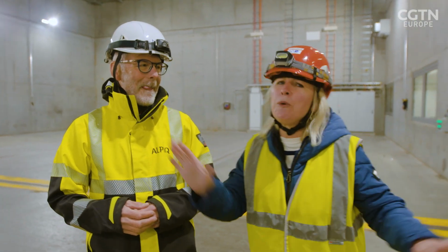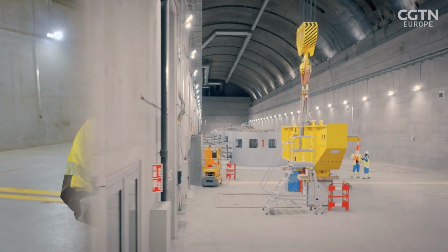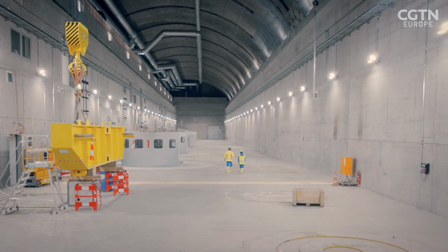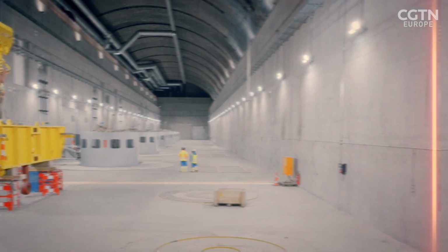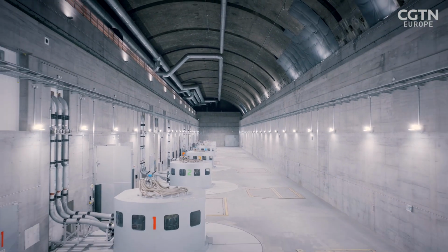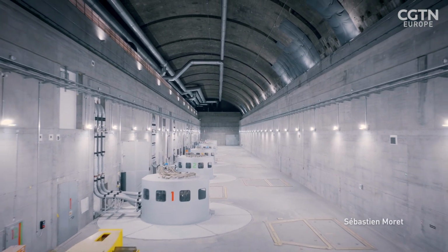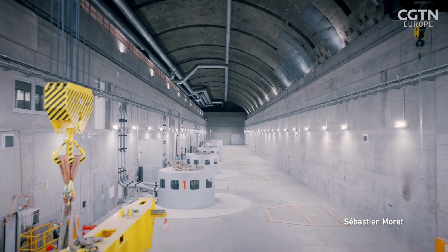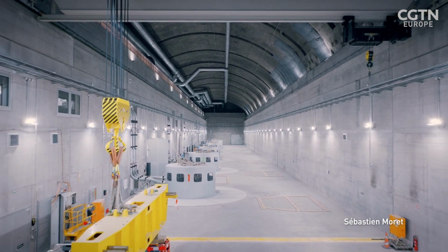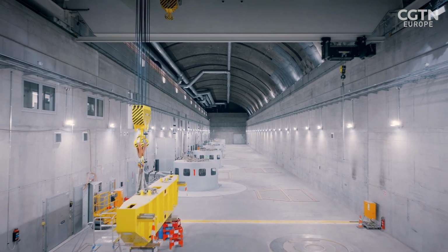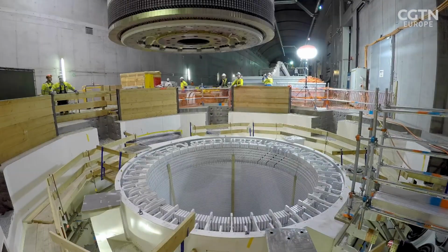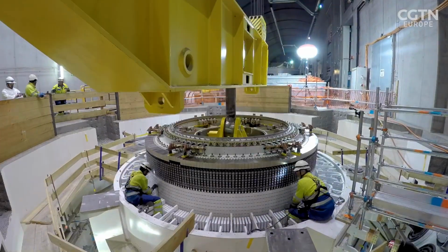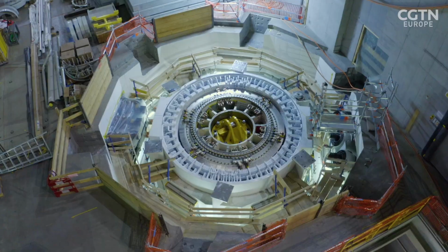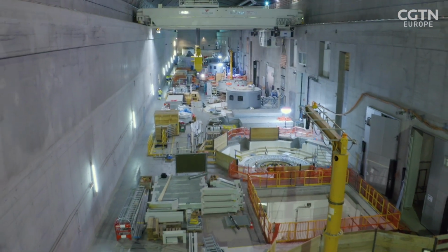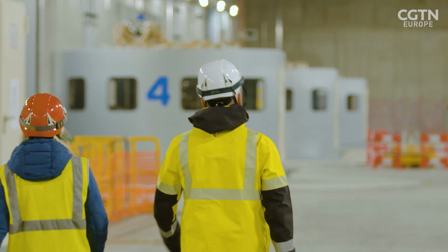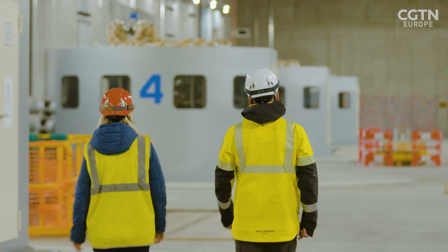Big numbers. They don't do small numbers here. Everything's big numbers. I'm on a tour of the Nant de Drance, a pumped storage hydro facility. In this huge cavern, you can only see the top of the machines. The whole generator pump turbine tree extends down below our feet over 3 floors. The reason the cavern is so big is so a crane can lift these giant machines up to the top floor for maintenance. So here we are at the top of the machine, now machine number 4.